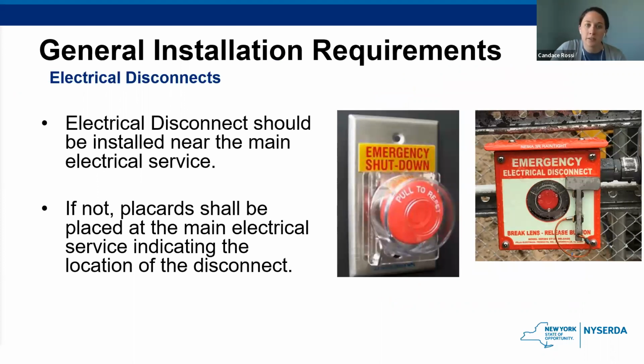So here we're going to start moving into the general installation requirements. And we'll begin with the electrical disconnects requirements. So electrical disconnects are extremely important to first responders, and they should be in a secure location with signage to direct the fire department to the proper place. Even though you may shut down the energy storage system, the stored energy inside the batteries does not just dissipate. So that is a key point to be aware of.